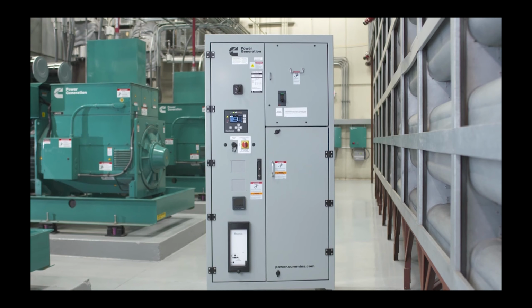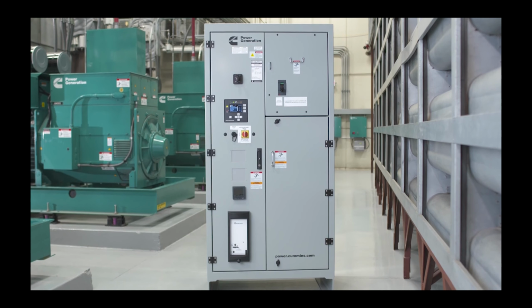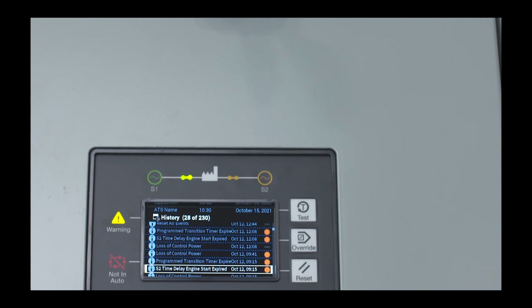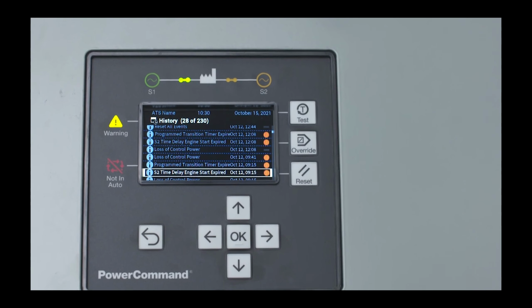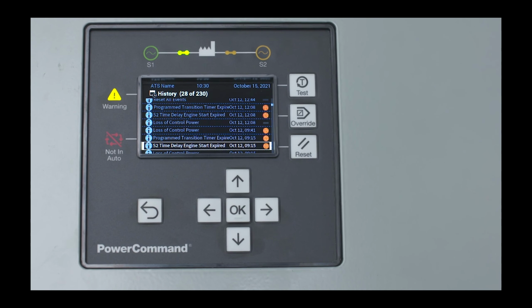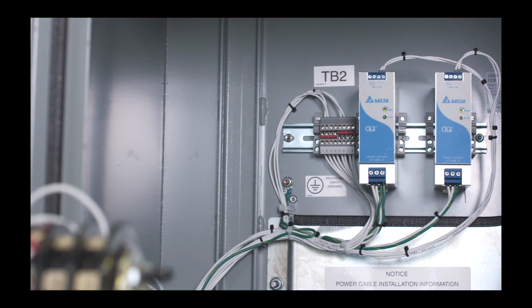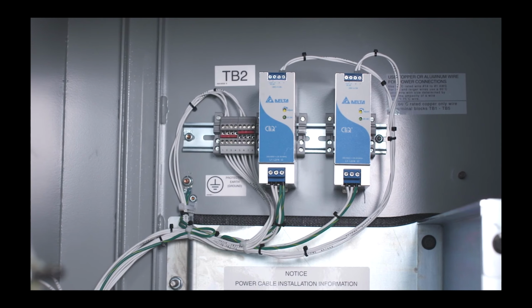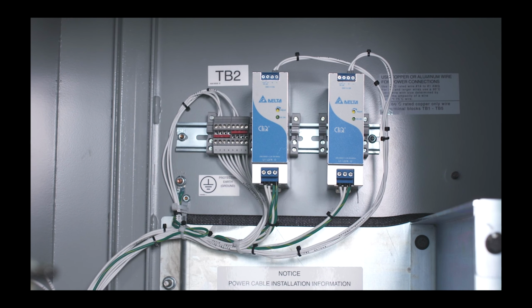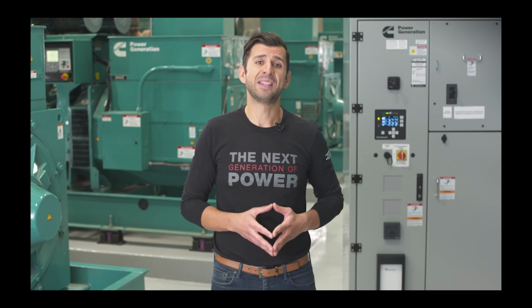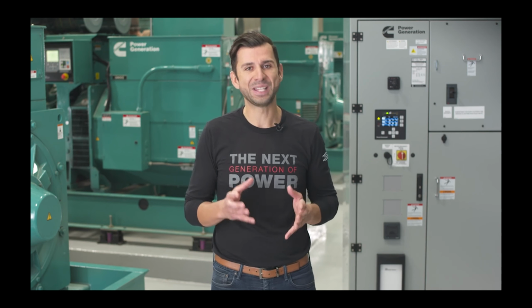A crucial part of any transfer switch is the control. The X series transfer switches are equipped with a sophisticated, fully integrated control, the Power Command 80. It is a single control, fully integrated for complete simplicity and reliability. The sensing, the control algorithm, power quality metering, and load management and communication are all in the control. No need for any additional hardware or complicated setups. And to maximize reliability, the control can be connected to three separate diode-isolated DC power sources. For your facility, this means higher reliability, ease of connectivity, and serviceability.